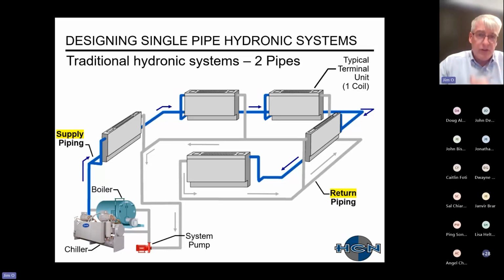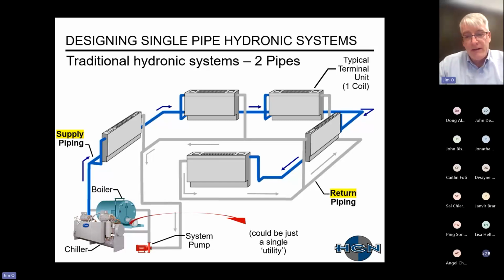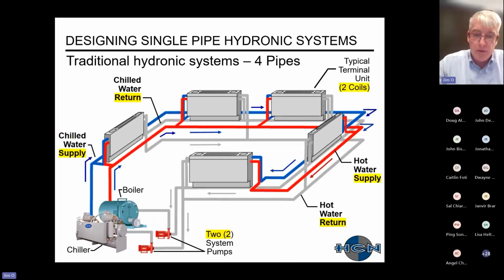So quickly, just to explain the different hydronic systems, this schematic here shows a traditional two-pipe system. Just going through the components of it, you have a central boiler for heating, a central chiller for cooling. You have distribution piping, where you have two piping systems, supply and return. And then what I'm calling terminal units, with one coil, are providing the heating and cooling to your spaces. They can be fan coils, they could even be air handlers, et cetera. So that's a two-pipe system. Just realize also that you could have a changeover system. This could be just cooling only. This one here is a changeover with heating and cooling.